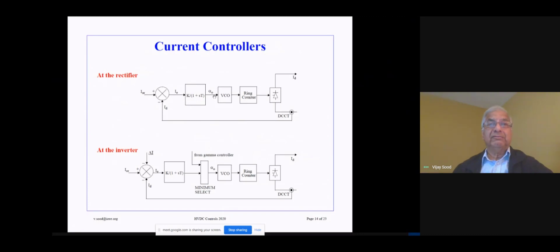This generates a firing order, which goes into a voltage controlled oscillator, and a ring counter follows that. The purpose of the ring counter is to take the pulse train coming out from the voltage controlled oscillator and distribute the firing pulses to the various valves inside the converter. So this is the rectifier current controller.